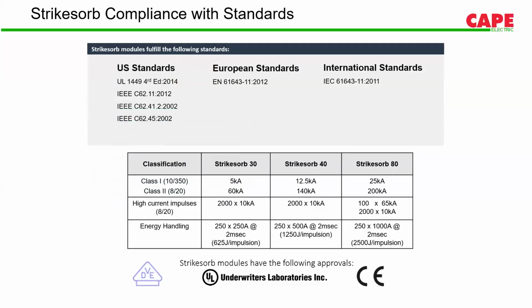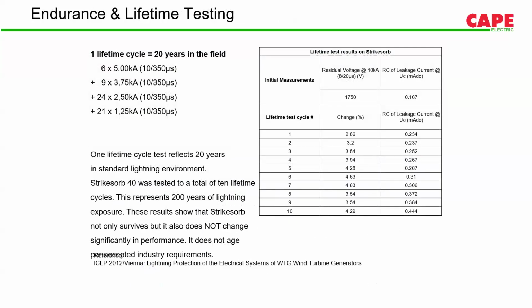For all our SPDs, Strikesorb 30, 40 and 80, we have tested with 2000 back to back switching surges of 10 kiloampere each. For an SPD to withstand 2000 surges, it should have very good quality protective components. So you can see the energy handling capacity of these SPDs. This is the general life cycle of an SPD. One life cycle test reflects around 20 years in a standard lightning environment. Strikesorb 40 was tested to a total of 10 lifetime cycles.